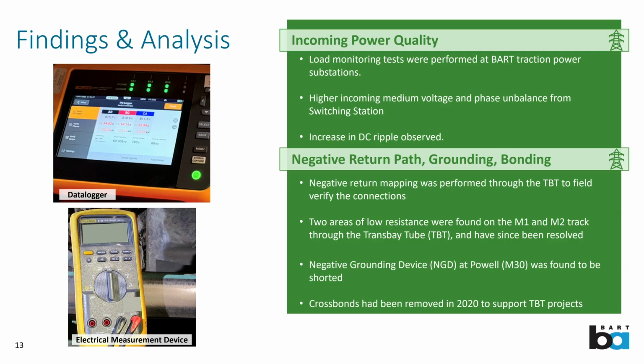On the top left, you'll see a photo of an actual PQA from this investigation, PQA being Power Quality Analyzer. These are also known as data loggers. The load monitoring tests were performed to look at the incoming power quality, so looking closely at the incoming currents and the incoming voltage into that substation, as well as recording any harmonics. If you're not familiar with the term harmonics, you can think of them as unwanted frequencies. Now, harmonics are not really of interest to us on the DC side, however, they are on the AC side, but they could result in unwanted frequencies on the DC side and a change in the DC ripple.